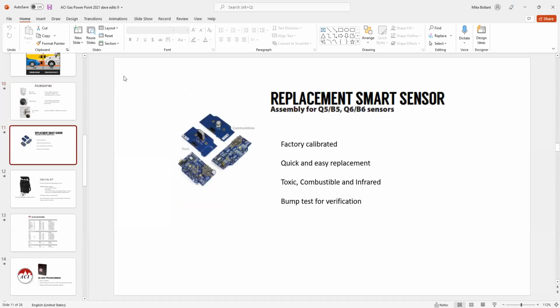Let's see here. Replacement sensors. It's kind of a neat feature. Let's say you've got a job out there, and I'll just use the Q5s for example, you've got CO and NO2, and after 5-6 years you go out, do a bump test on it, and you don't believe the sensors are working correctly. You don't have to replace the whole unit. All you have to do is replace this little microprocessor board in there. Basically that's taking 4 screws off the front, pulling it off, taking 2 screws off the microprocessor board, pulling that out, and putting the new microprocessor board back in. Make sure everything's powered down, put your screws back on top, fire it up, and everything's pre-calibrated. What we really recommend is quickly doing a bump test, and away you go. It should work pretty seamlessly. We've done quite a few of those in the past. Any questions on this?